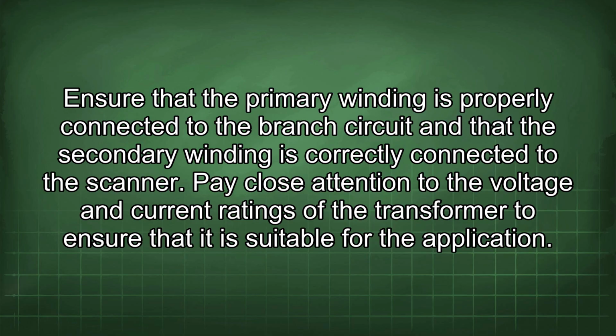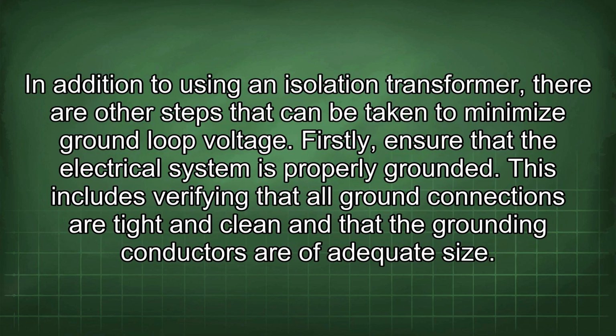Ensure that the primary winding is properly connected to the branch circuit and that the secondary winding is correctly connected to the scanner. Pay close attention to the voltage and current ratings of the transformer to ensure that it is suitable for the application. In addition to using an isolation transformer, there are other steps that can be taken to minimize ground loop voltage. Firstly, ensure that the electrical system is properly grounded. This includes verifying that all ground connections are tight and clean and that the grounding conductors are of adequate size.